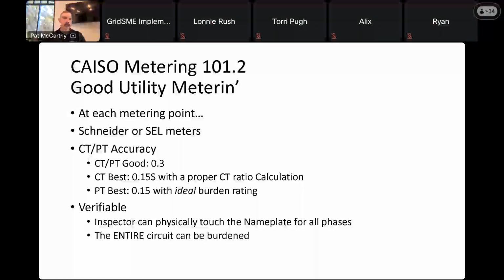Your utility, which brings its own set of requirements as a retail billing entity, is not concerned with your wholesale bulk transfer of energy out to the system. They are concerned with the very small amount of energy that comes back into your system when you're not producing energy. So they want that CT to be accurate even when you're only pulling 10 amps into your facility. That's like 1% of your CT nameplate, and that's not actually doable under any CT standard. I think the CT standard is C57.13 or something. Anyway, one way to get around that is to get attestation from the manufacturer that it is actually 1% accurate. But the main way to get around it is by sizing your CT exactly right.